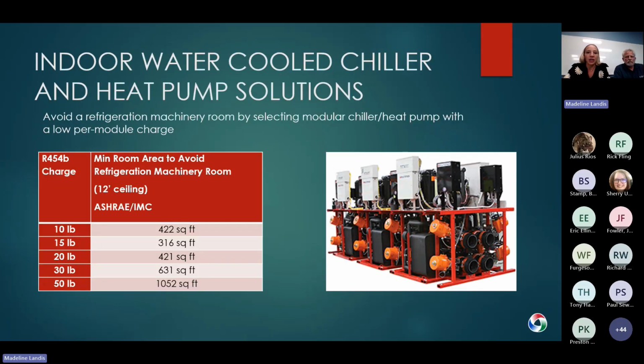Some other application challenges that we've experienced is using indoor water-cooled chillers and heat pumps. Very similar to VRV applications, the first step is understanding the volume of the mechanical room and understanding how much refrigerant can be used before it's considered a machine room. An easier way to assure that you're within these limits is to use modular chillers because they have smaller refrigerant charges per module.